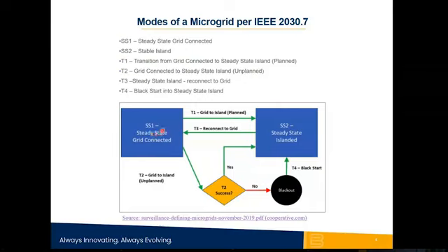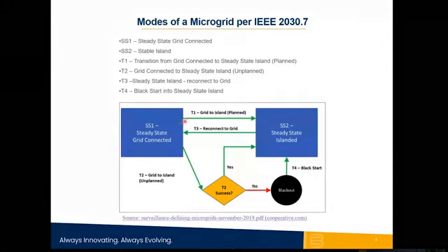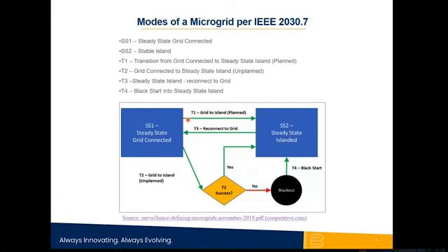because the grid is going to be stressed at that point in time based on demand. Or it may go further to say, I don't want you to disconnect, but I want you to start up all your generators of various types and export power to the grid. So both of these could be a planned transition from grid connected to steady state.